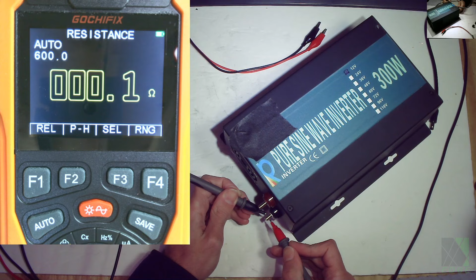If you probe the inverter and you see a readout that looks like this, I'm going to do it again. You can see it counting down and going down the ranges, and it goes into basically 0 ohms. Essentially, it's saying 0.3 of an ohm, but in actual fact, it's probably pretty much 0 ohms. It's just showing you the wires that are connecting the test probes. Essentially, that's 0 ohms, and it's a short circuit.